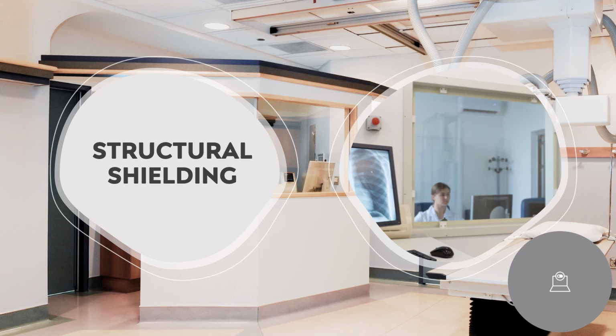The design of the X-ray department and rooms is for the protection of the general public, the patients, and imaging personnel. So when we're looking at how the rooms are built, the primary barriers are those that are in the path of the direct X-ray beam. So say the wall right behind the wall Bucky, that's a primary barrier because the X-ray tube is facing that wall. These contain 1.6 millimeters or 1/16th of an inch of lead, and they need to extend from the floor by 2.1 meters or 7 feet upward.